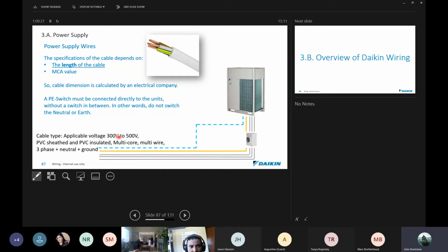Okay, cable type applicable to 300 to 500 volts, PVC sheath and PVC insulated, multi-core, multi-wire, three-phase plus neutral plus ground. Something that I'm glad I'm seeing a lot more of is separate earth cables pulled into units. On a lot of Surfex cables that come with the earth, that little earth wire that's in there is often not enough earth to protect a unit, and we need sufficient earthing, particularly with electronic components. So I'm glad that we've seen a lot more installations where separate earth cables are pulled in, and it is definitely a move in the right direction.